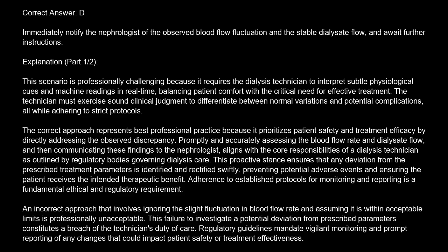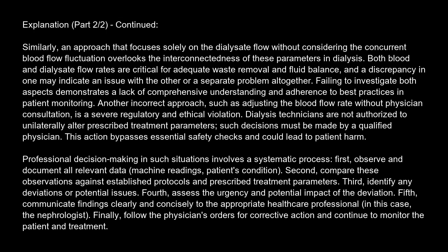An incorrect approach that involves ignoring the slight fluctuation in blood flow rate and assuming it is within acceptable limits is professionally unacceptable. This failure to investigate a potential deviation from prescribed parameters constitutes a breach of the technician's duty of care. Regulatory guidelines mandate vigilant monitoring and prompt reporting of any changes that could impact patient safety or treatment effectiveness.